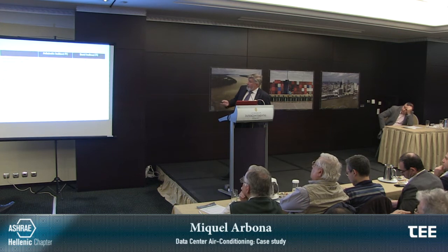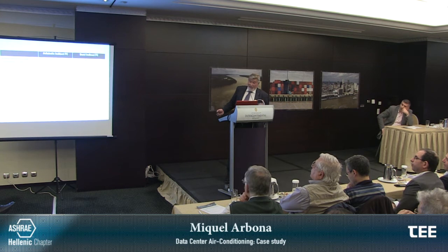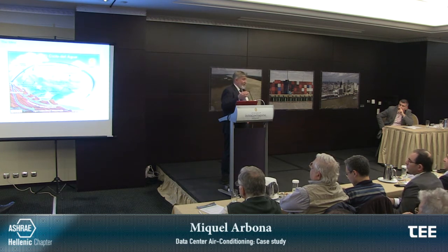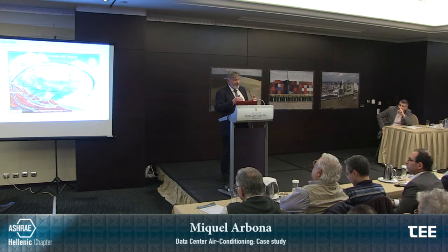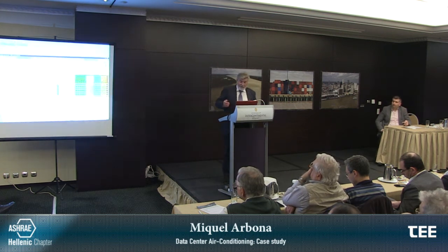So if you make the numbers for the whole year, we have a reduction of 30% of electrical demand, and of course the system is not magic. Something happens. What happens? We are evaporating water, so you are using water, and this could be a problem. But at that time, this was planned in Santander, which is in the north of Spain, a place where it rains a lot. People are constructing data centers in Finland, in Scandinavia, where it's very cold outside, because you have this cold to cool down the data center. But another opportunity is to use the water from the rain, and this is what we were using at that point.